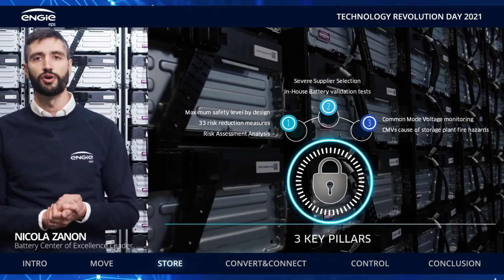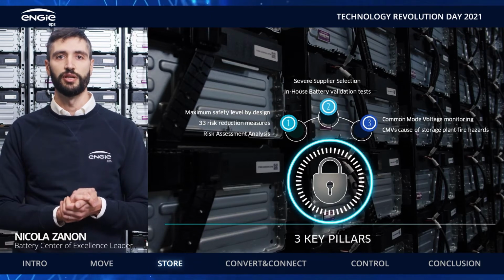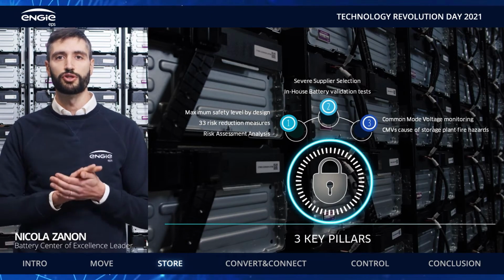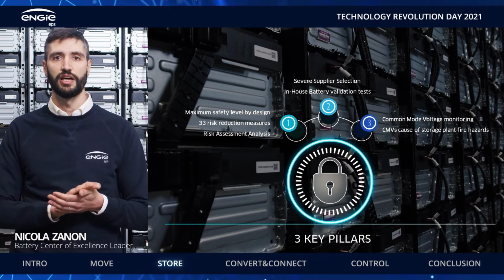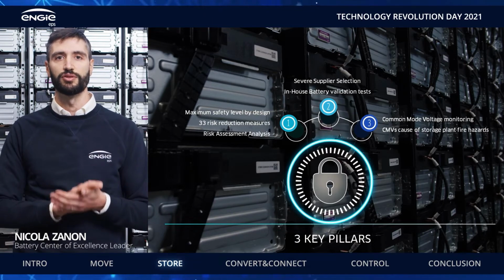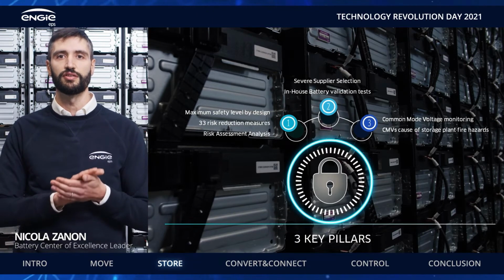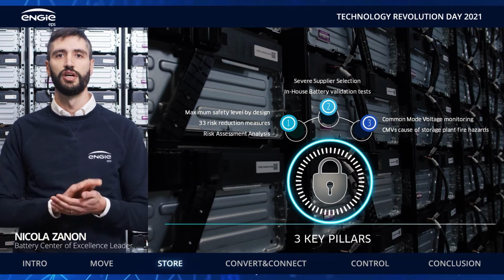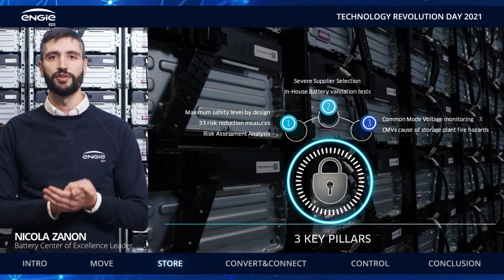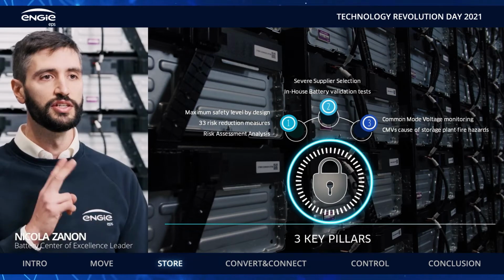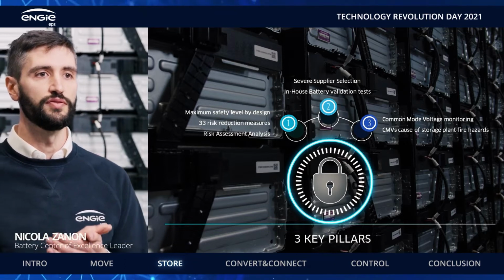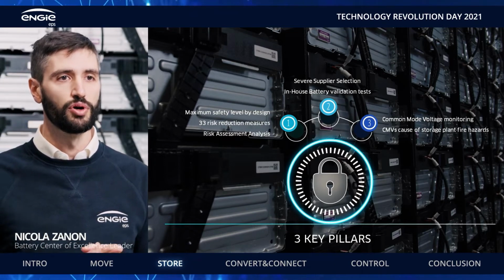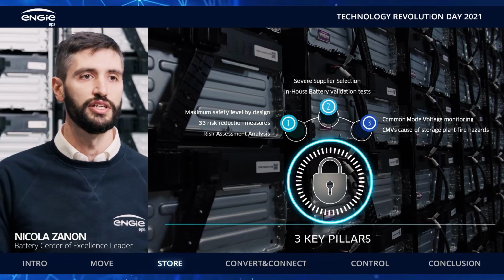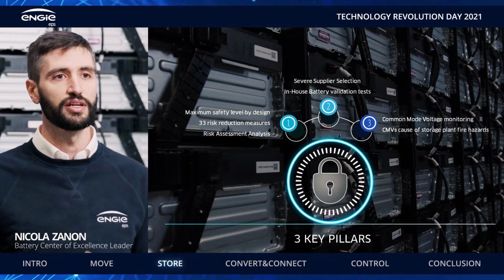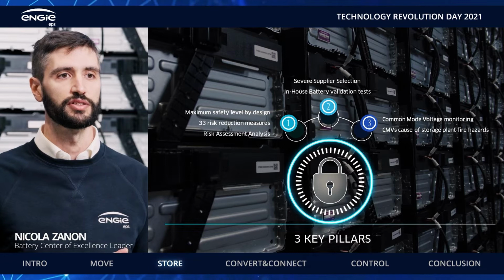We have a strong focus on battery safety based on 3 key pillars. First, we pursue the maximum safety level by design. In any battery container, we implement and set 33 risk reduction measures based on a project-specific risk assessment analysis. Second, we perform severe supplier selection through audits and in-house battery validation tests to verify declared performance and safety parameters, reducing long-term technological risks.